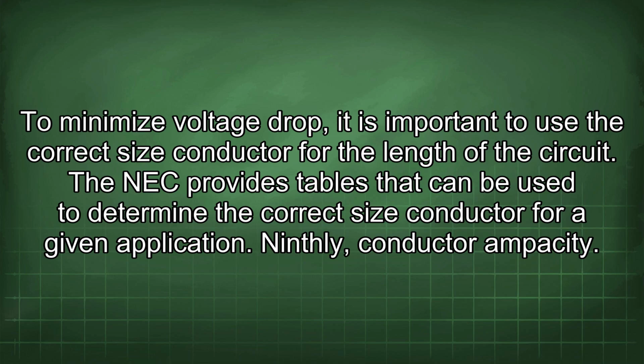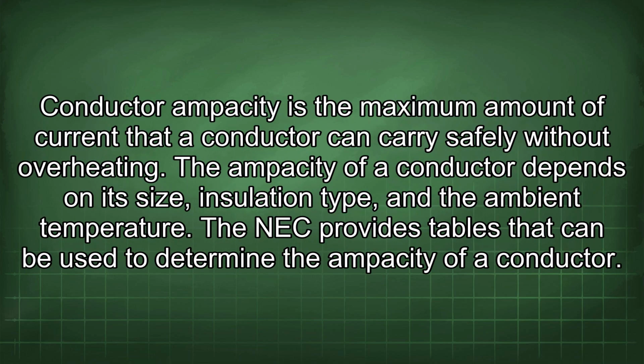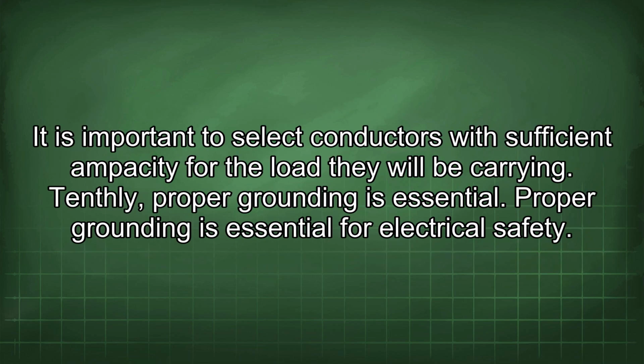Ninthly, conductor ampacity. Conductor ampacity is the maximum amount of current that a conductor can carry safely without overheating. The ampacity of a conductor depends on its size, insulation type, and the ambient temperature. The NEC provides tables that can be used to determine the ampacity of a conductor. It is important to select conductors with sufficient ampacity for the load they will be carrying. Tenthly, proper grounding is essential.